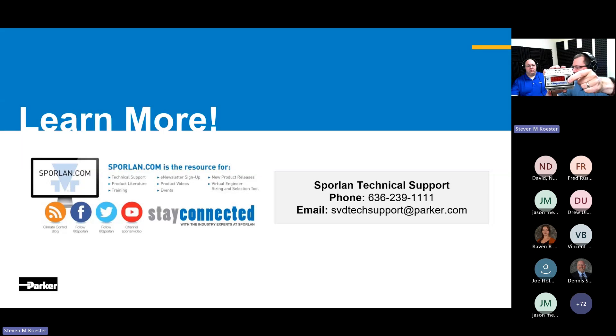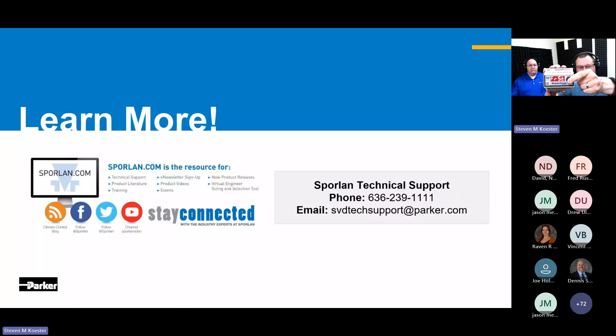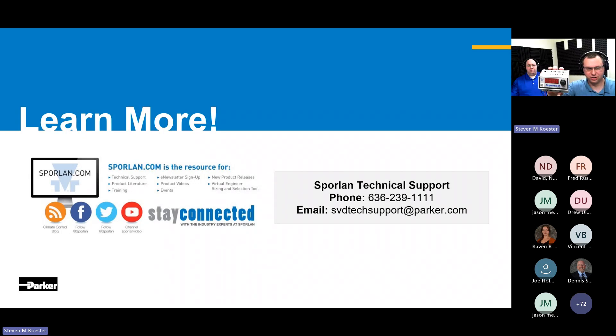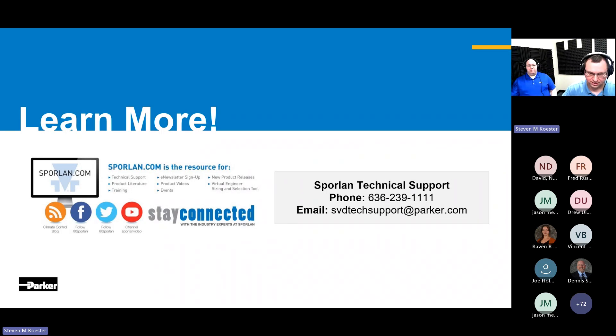If the Kelvin 2 turns off, push and hold this button, continue to hold it, and go ahead and power it back on. It's going to say FRST. Once you let go, it will finish booting and it'll be back asking the number of steps to the valve, and you can go back through the startup process from step one. That could be helpful if you're doing a retrofit or changing valves and you don't want to navigate the long menu — you can make sure the basics are set up correctly and go from there. And that is the Kelvin 2 platform in a nutshell.